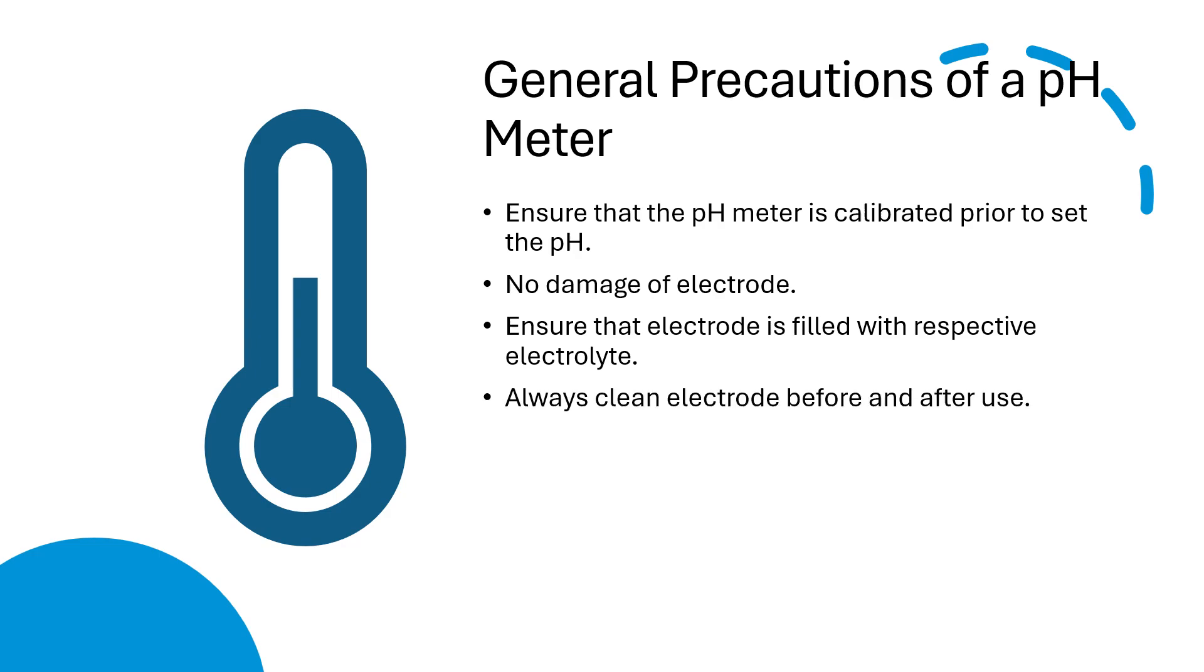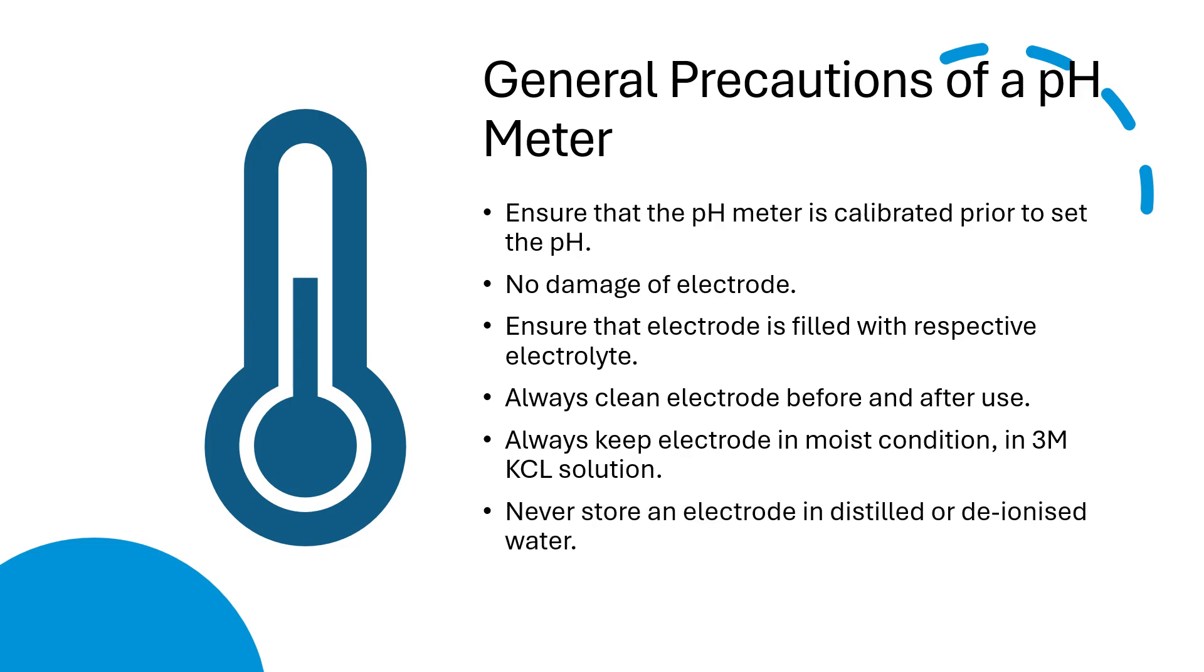Always clean the electrode before and after use. You can use purified water in such cases. Always keep the electrode in moist condition in 3 molar KCl solution. Never store an electrode in distilled or deionized water because this causes the migration of the filled solution from the electrode, thus it will decrease the response to hydrogen ions.